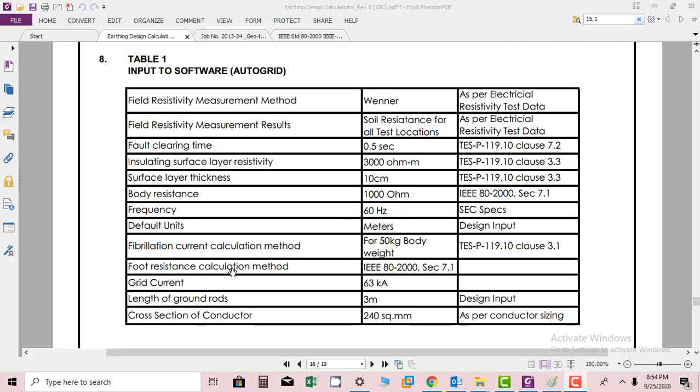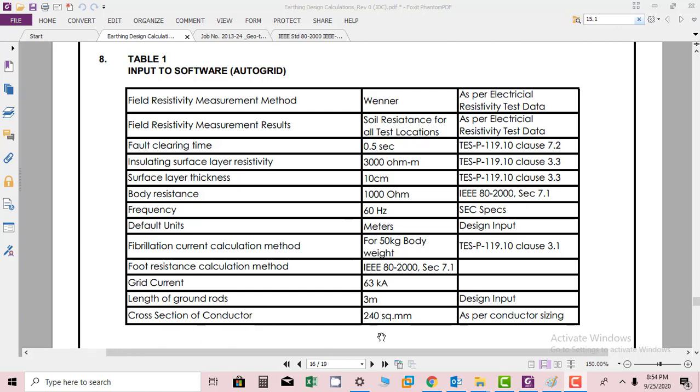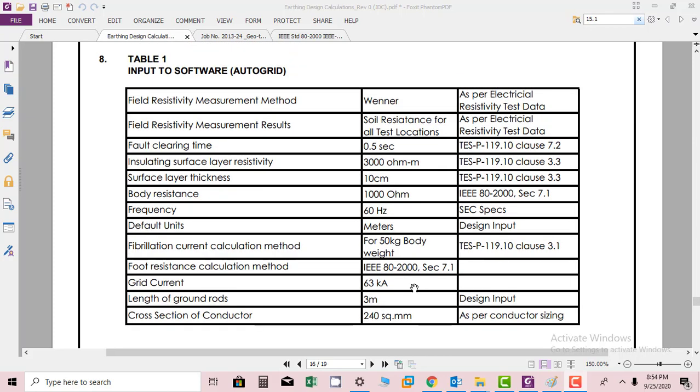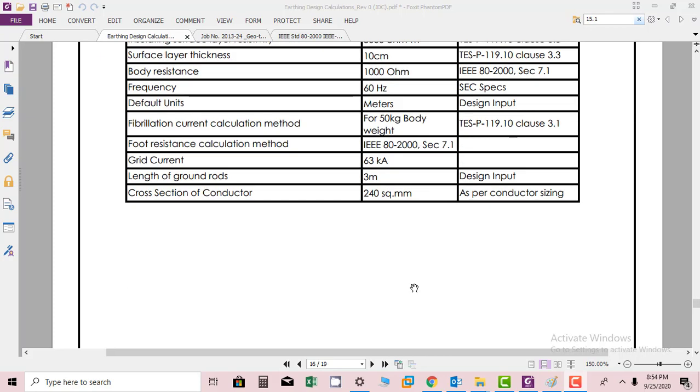Foot resistance calculation method is IEEE 80-2000 section 7.1. Fault current is 63 kA as provided by the client. Length of ground rods is 3 meters as requested by the client. Cross section of conductor is 240 square mm as per conductor sizing calculation that we have done. So this is the input to software.